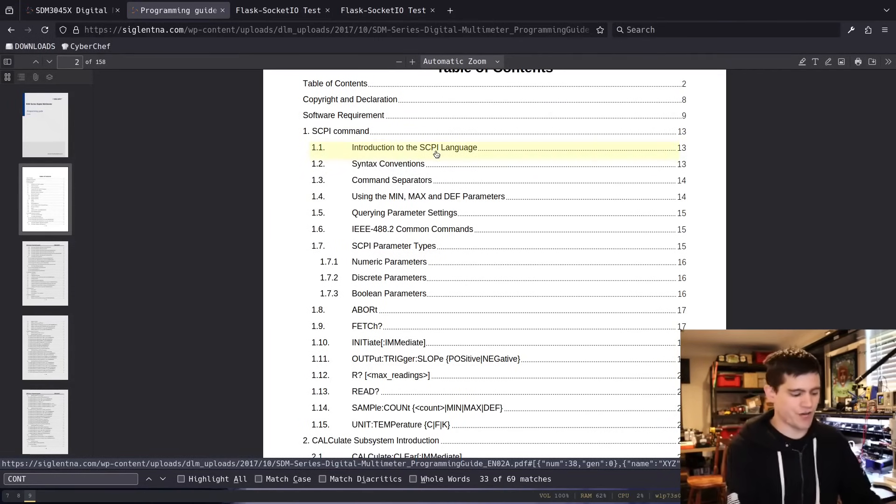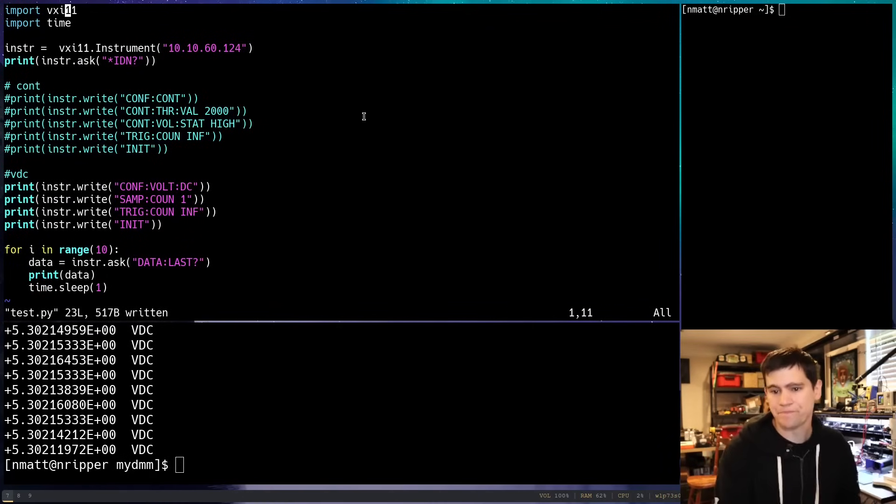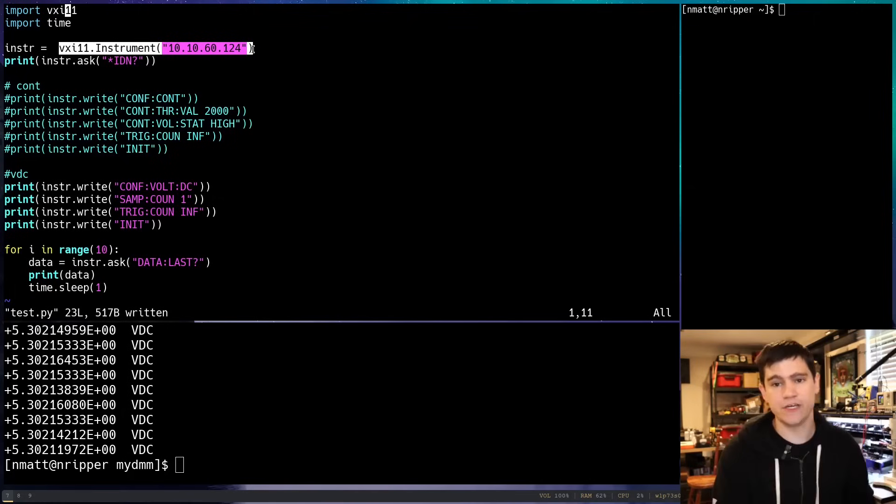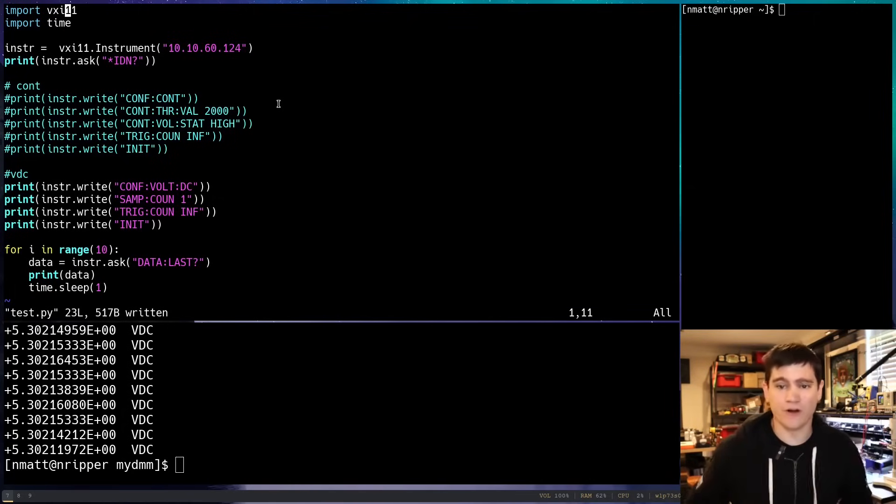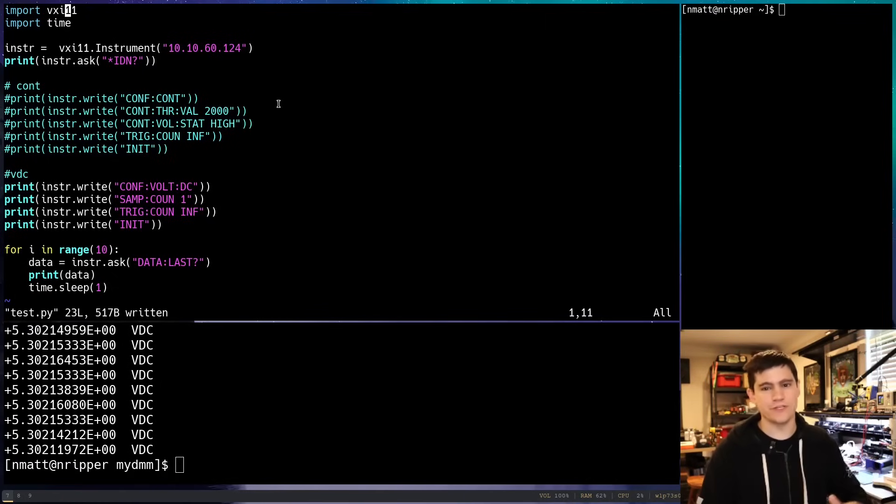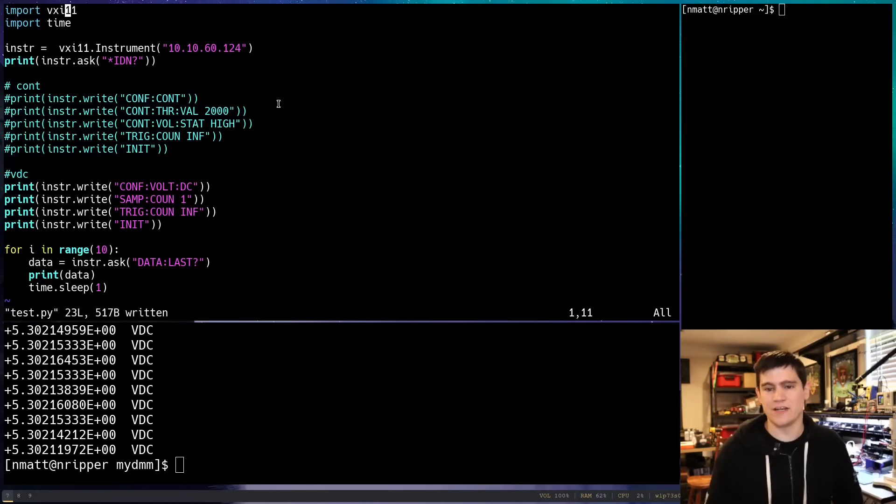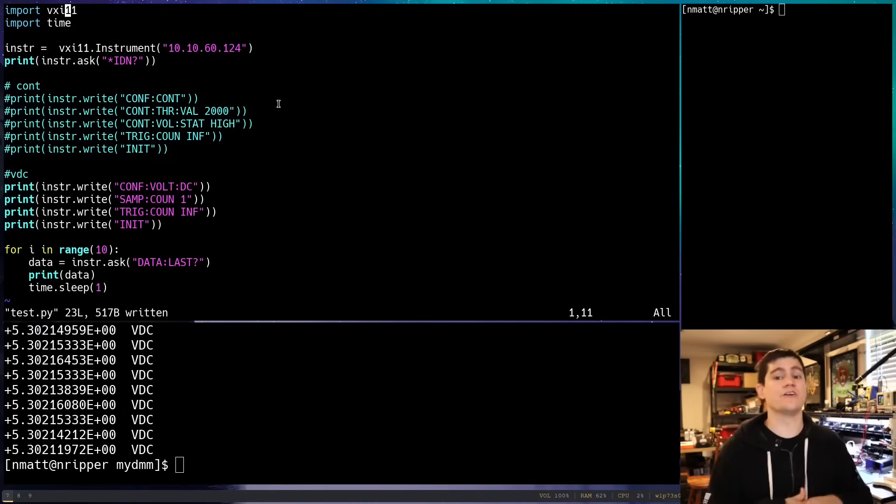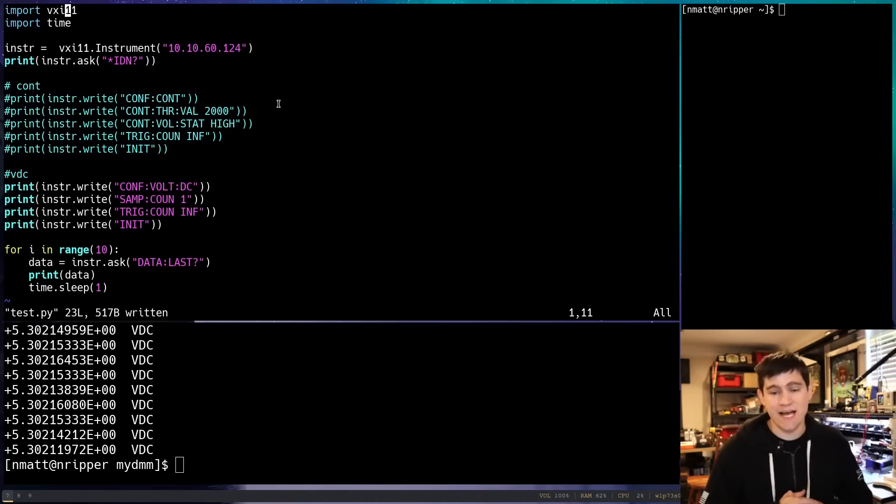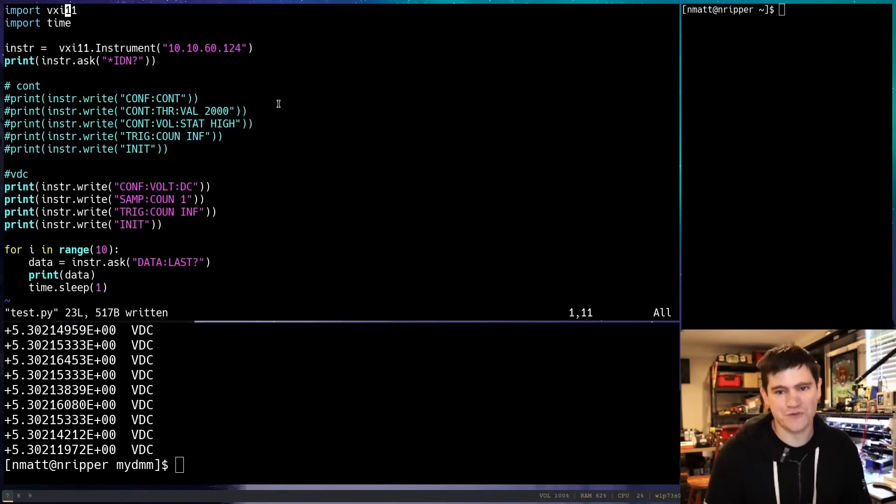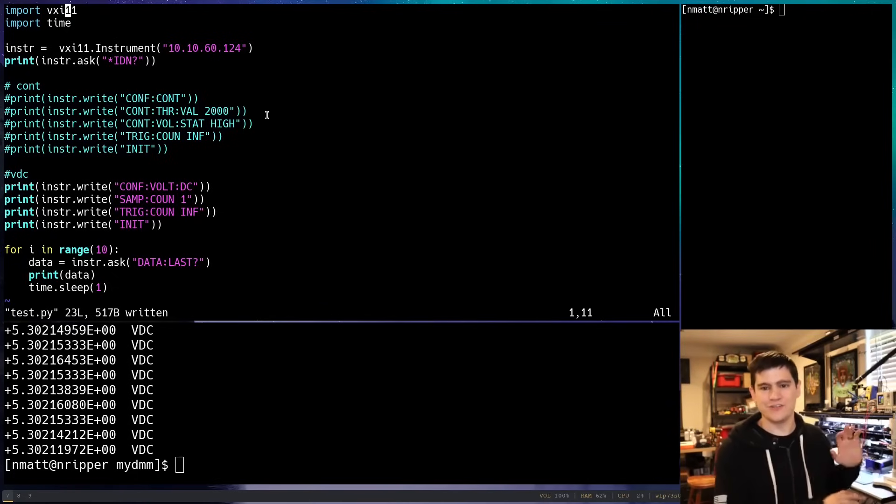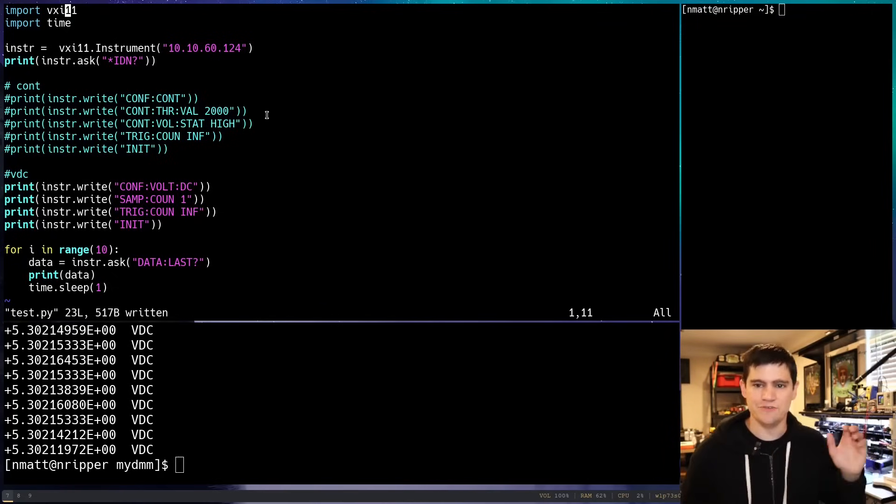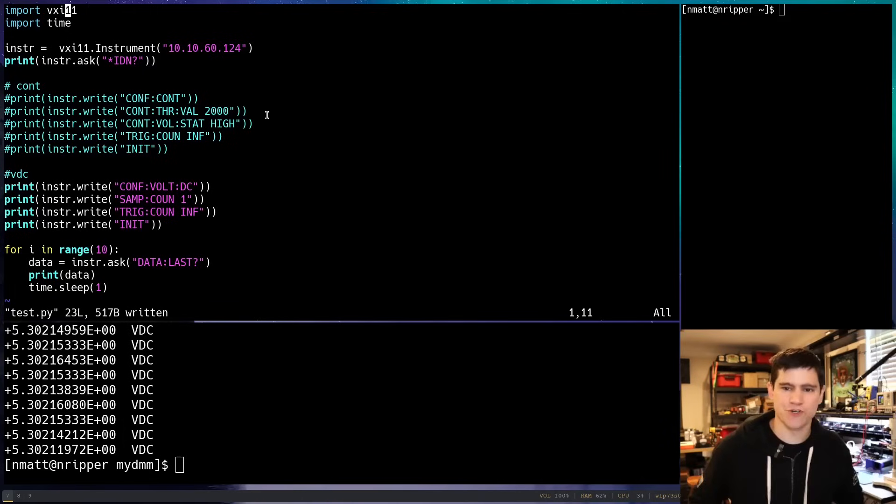You'll see here that we have this library VXI. VXI 11 is some kind of abstraction layer for those SCPI commands. It's just another layer of abstraction on top of that. What we're using is we're saying, hey, go connect to this IP address. It runs on the default port. By the way, you should definitely not have this stuff on the internet because there's absolutely no authentication in this protocol. This is meant to be on a local network, potentially even a network that doesn't have internet access at all in a lab environment.